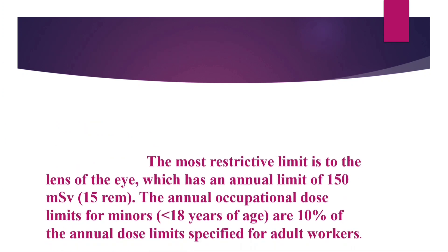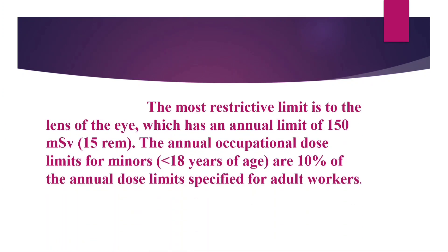Now let's see the explanation. The most restrictive limit is to the lens of the eye, which has an annual limit of 150 mSv, or 15 rem. The annual occupational dose limits for minors, that is those less than 18 years of age, are 10% of the annual dose limit specified for adult workers.